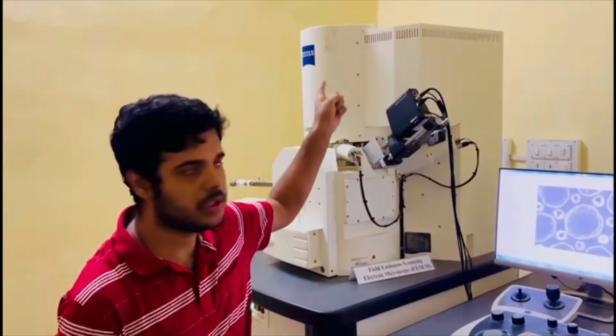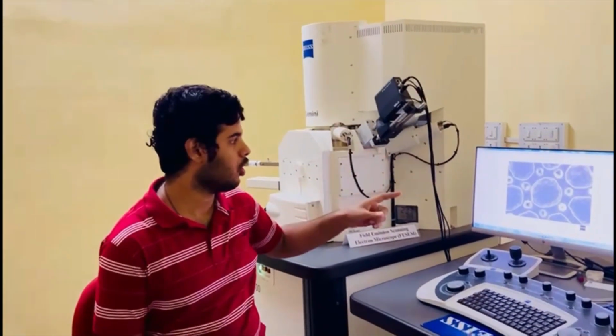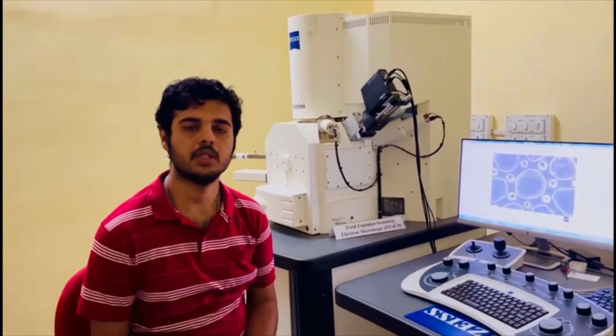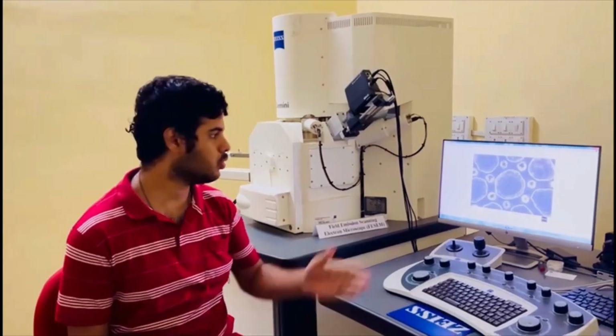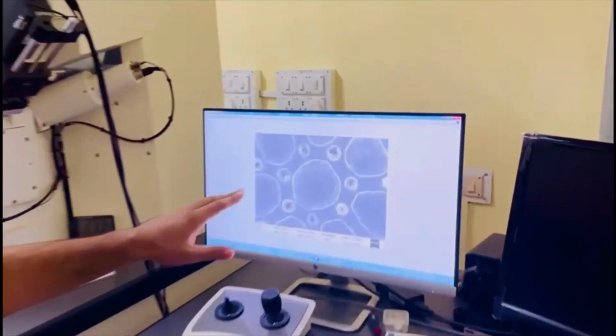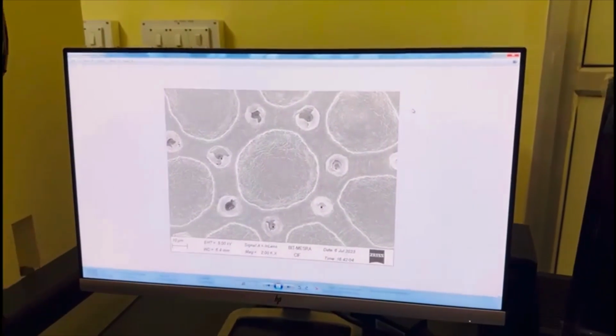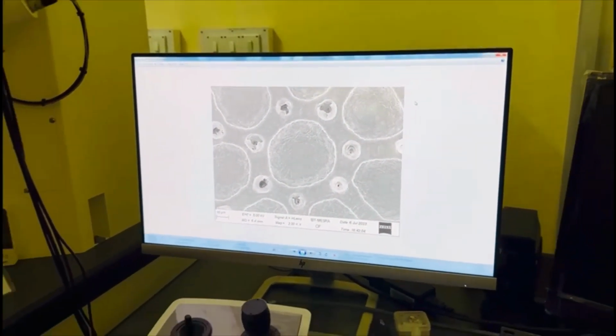The differences between SEM and FESEM are as follows. Here there is a FEG gun instead of a thermal gun. Also, the gun and the chiller remain on for 24 hours, and as you can see in the images, FESEM is of higher resolution and the magnification is higher compared to SEM.